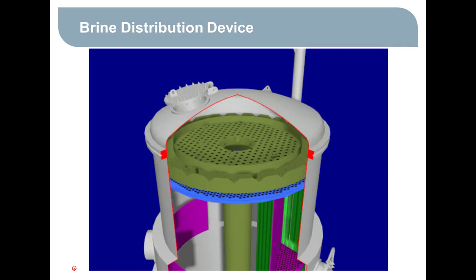If you look a little more closely at the top, you can see this brine distribution device, you see the central recirculation pipe coming up through the middle, and the brine flows up through that pipe and spreads out on that top perforated plate, and then you can see some overflow weirs, and there's a second plate underneath. And basically those two plates distribute the recirculating brine evenly across the whole cross-section of the evaporator and around the inner circumference of each tube. Again, there's a tube bundle. We've taken the tubes out of the picture here to make it clear, but there's a whole tube bundle in there.